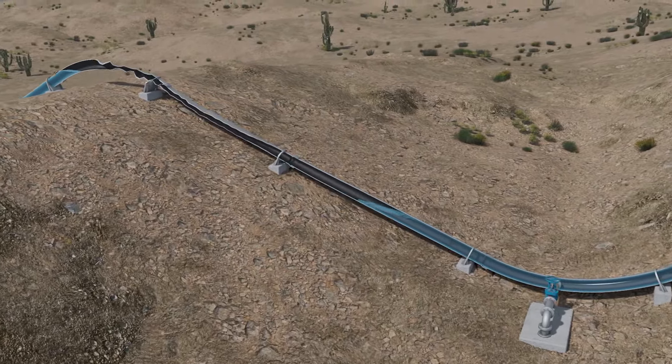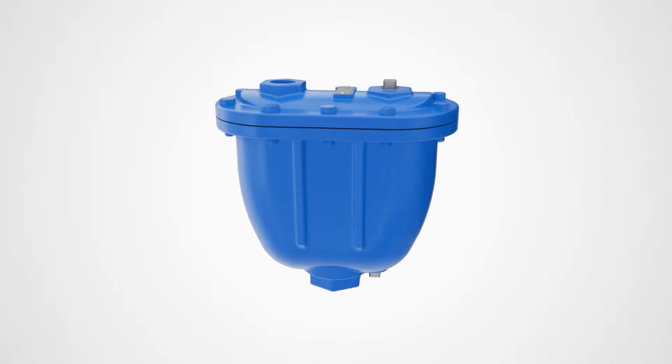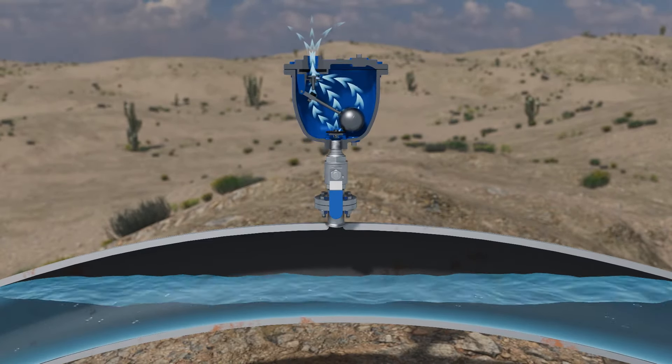In the worst case scenario, this can even cause the pipe to collapse. But with Val-Matic's combination air valves, you can prevent these problems before they happen. The combination valve is designed to exhaust large amounts of air out of the pipe, ensuring that it fills with water before any pipe failure happens.